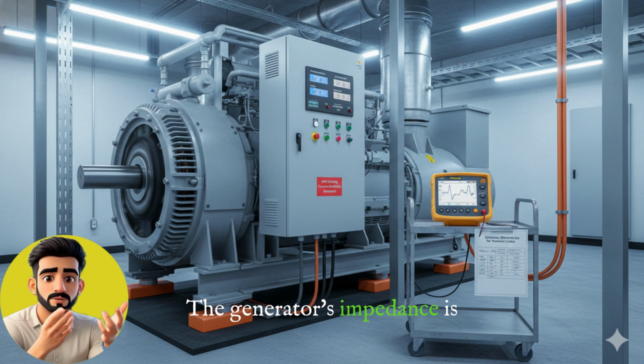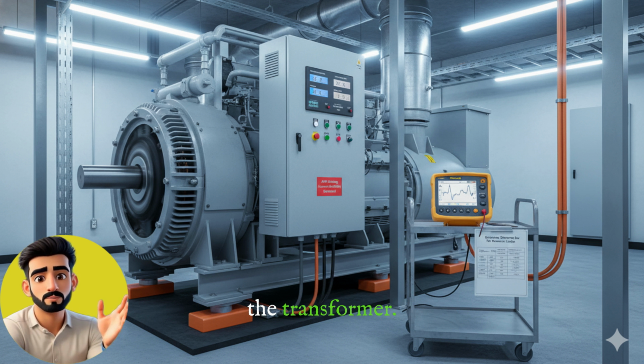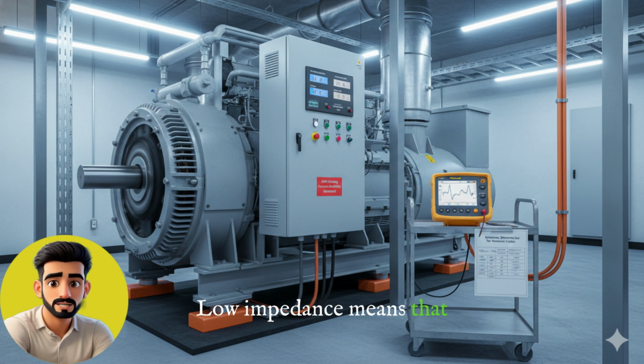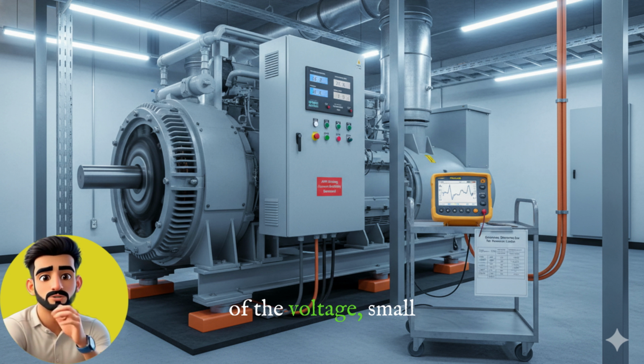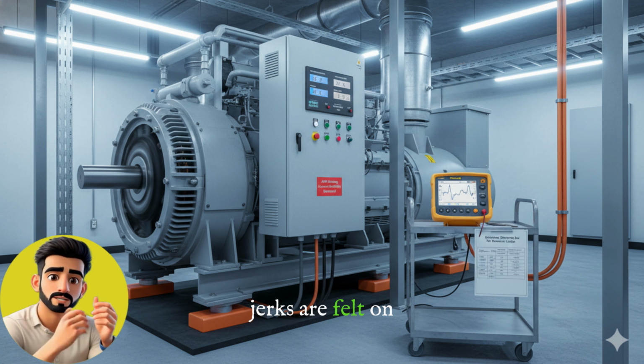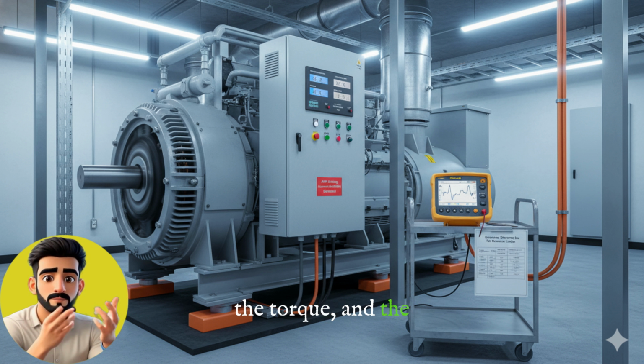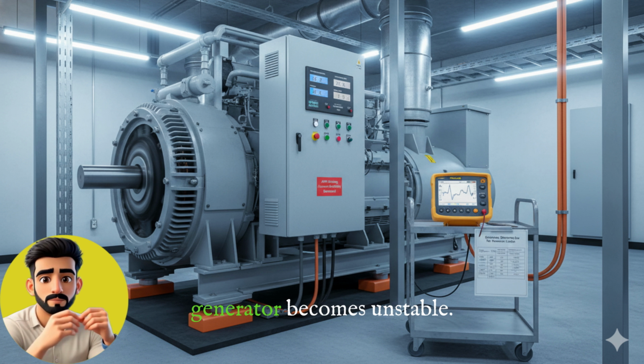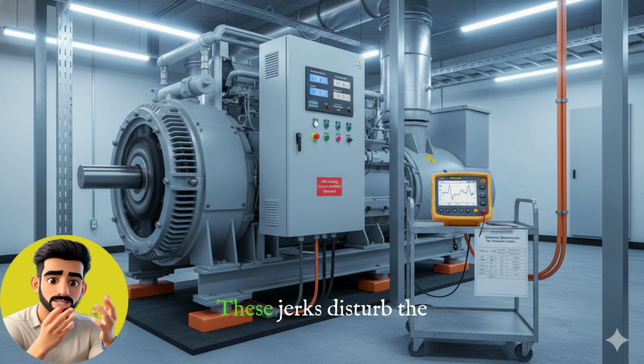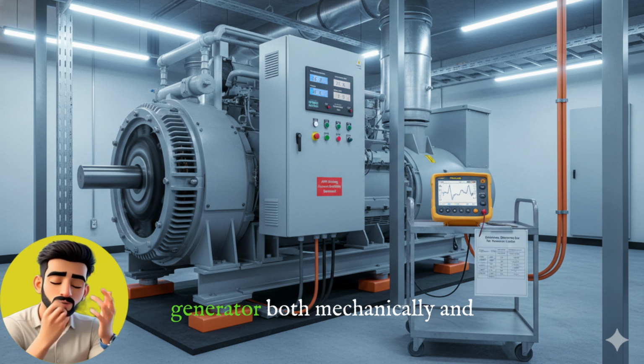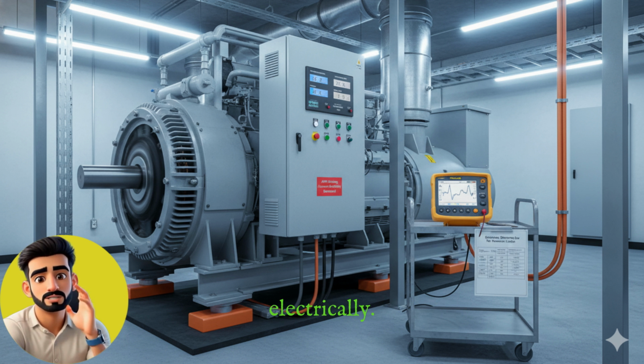The generator's impedance is much lower compared to the transformer. Low impedance means that harmonic current circulates more inside the generator. This distorts the shape of the voltage. Small jerks are felt on the torque, and the magnetic field of the generator becomes unstable. These jerks disturb the generator both mechanically and electrically.